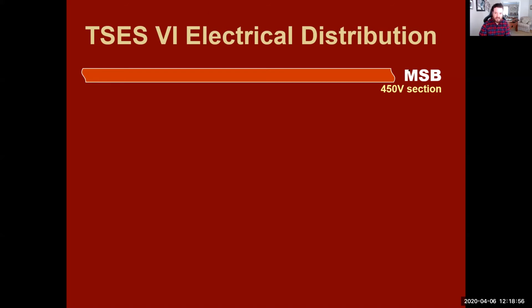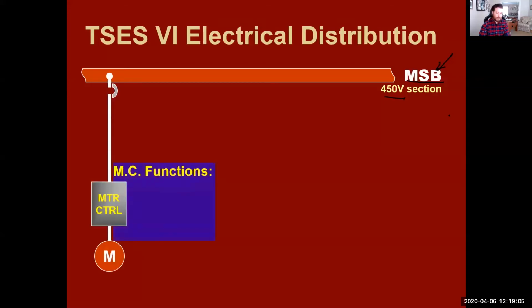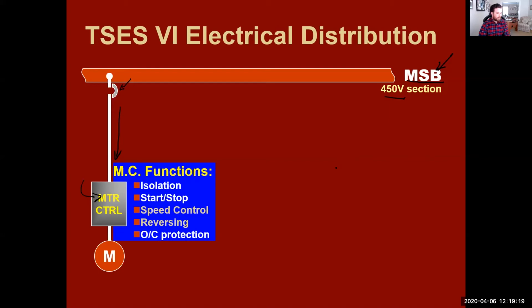Always on the top, you're going to have your main switchboard, your MSB. This is a 450 volt section. Now we have individual breakers that come off of it, and they go down feeding what's called a motor controller. Motor controllers have a couple different pieces to them: they're for isolation, start and stop, speed control, reversing, and overload protection.